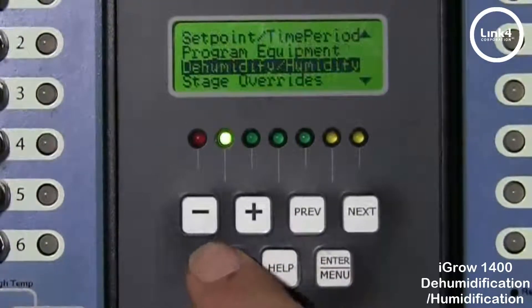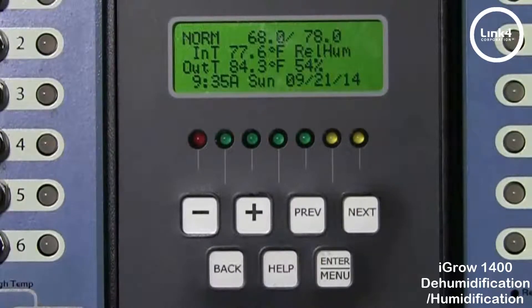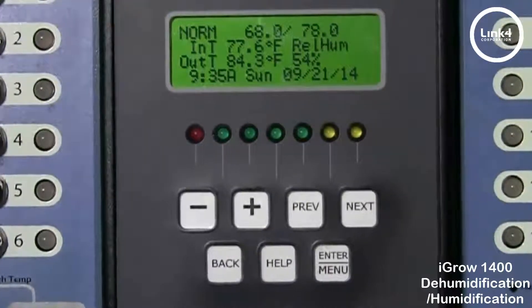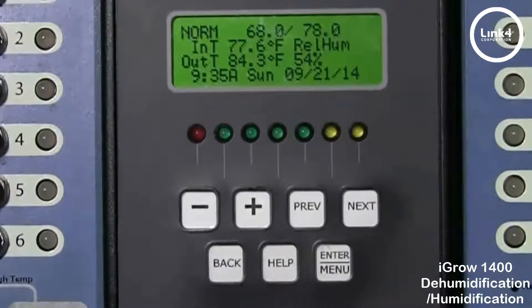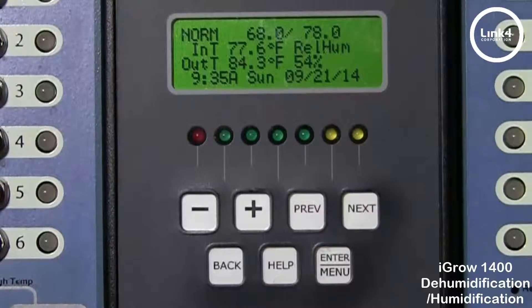If we go ahead and hit back to get to the home screen, we will show you what it looks like when the controller is in its dehumidification and humidification states. We'll do this by manipulating the relative humidity reading. Right now we are in the regular normal relative humidity state because 54% is between the 40% and 60% setpoints.